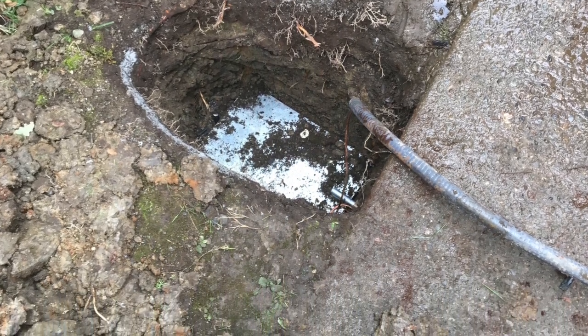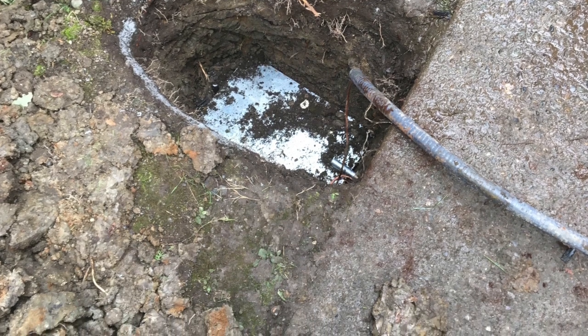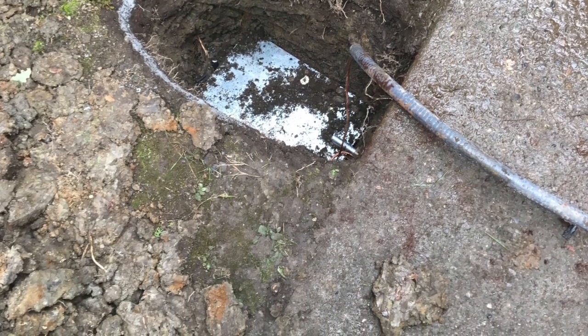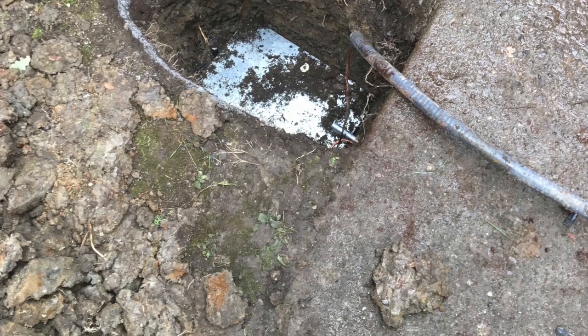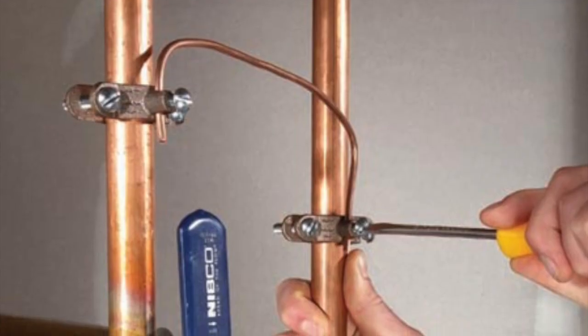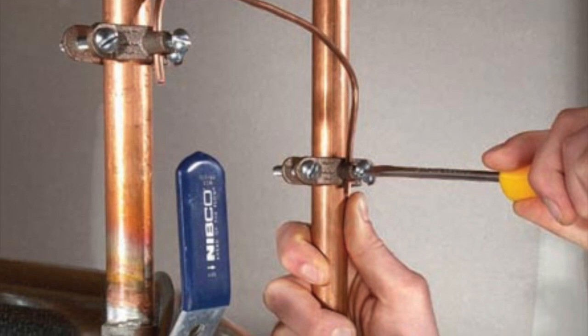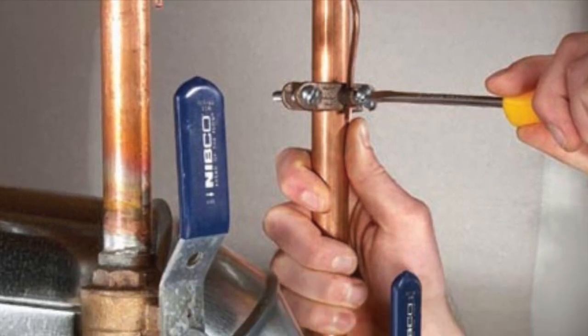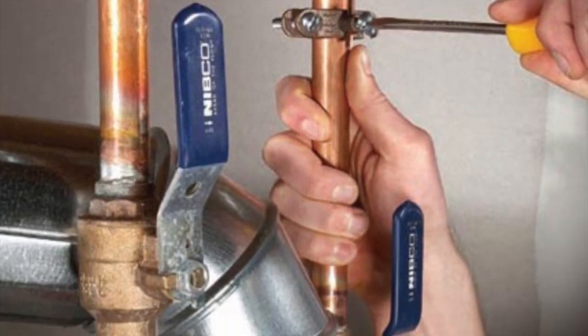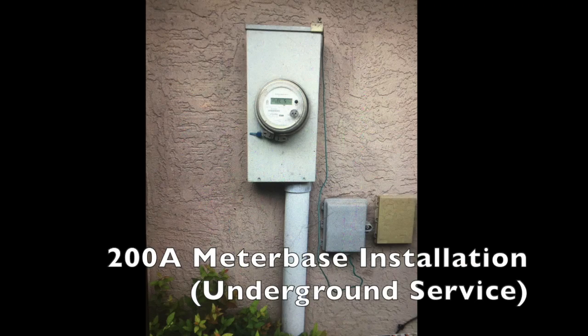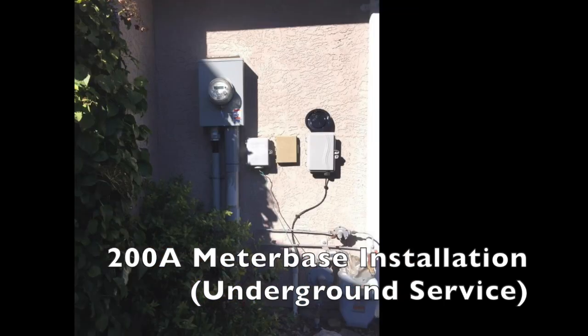So what we had to do in this is we had to take apart that concrete sidewalk in order to embed our electrical ground wiring. In addition, we also have to make sure that the water line and the gas lines are bonded in the home. This may require additional drywall removal. In this next image, this is the outside of a home with the original 100 amp meter base. In most cases, we do have to change the meter base, but in some cases we don't have to replace it because it already is capable of handling 200 amps.